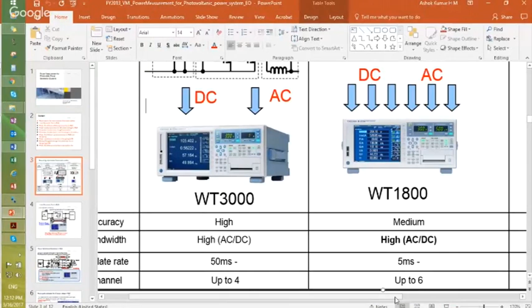And what about the WT500? The WT3000 is okay, WT1800 is okay, but WT500 is a 3 channel device—why is this used instead of relying only on the WT3000 and WT1800? The accuracy of WT1800 is 0.05%, but the accuracy of WT500 is 0.1%. So sometimes you don't require such high accuracy.